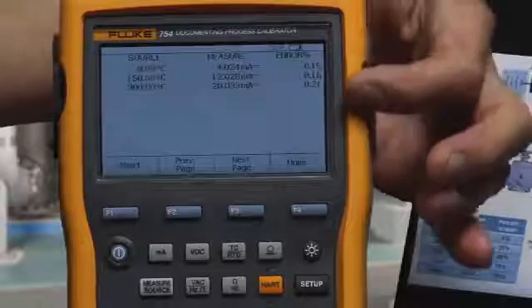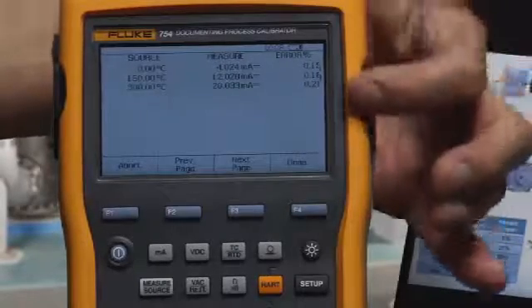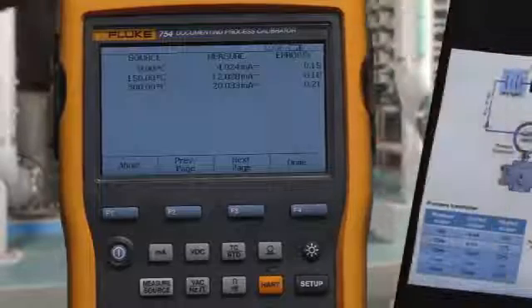None of the error percents are in reverse video, indicating that all the milliamp measured values were within the allowable test tolerance, and the transmitter passes the calibration test.